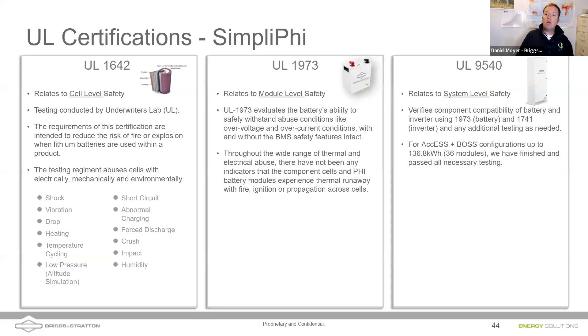What it is, it's a test that subjects our batteries to intense heating, where they wrap some of these battery cells in heating wraps, heat them to such a point that they go into a thermal runaway event, where thermal runaway is roughly defined as once we've heated it to a point that the battery has enough energy and heat being released from it that it causes adjacent batteries to go into their own thermal runaway and cascade into this uncontrolled, unmitigated thermal runaway. I'm not going to explain this whole chart on the right, but really what it showed with our batteries is that it self-extinguished, and we didn't get that kind of unmitigated thermal runaway.